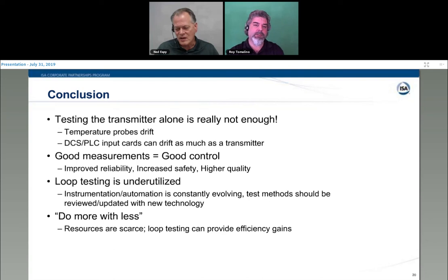If you're throwing them away, I don't know how much they cost. Let's say you're throwing away a $100 probe. If you could adjust your transmitter and get more life out of it, you save $100. But if they're making a bad measurement and it causes you to lose $1,000 or thousands of dollars of product, yeah, throw the probe away. It comes back to that common sense approach: do what causes the least harm.